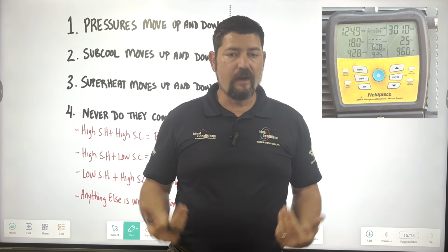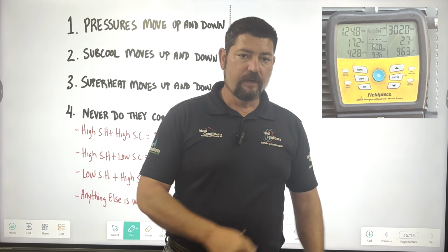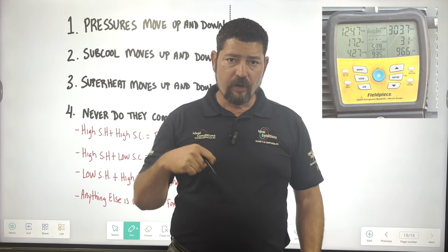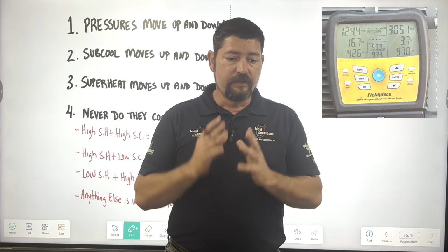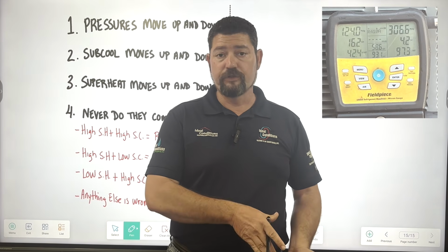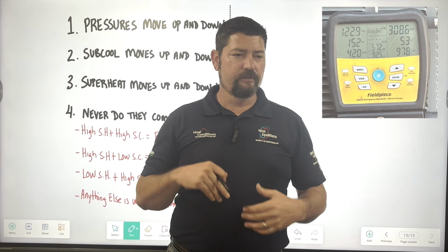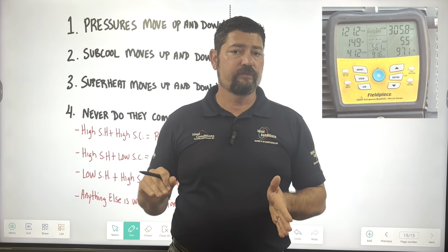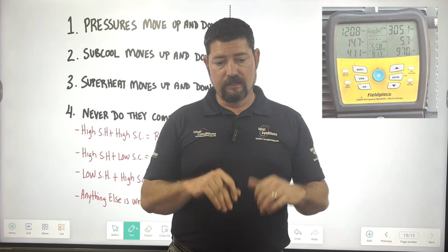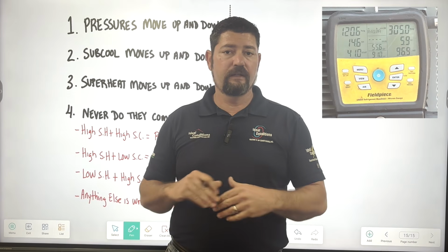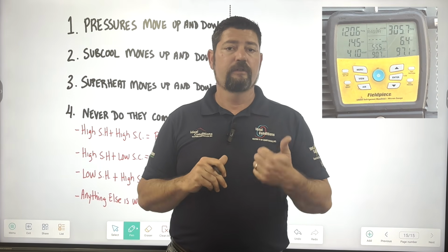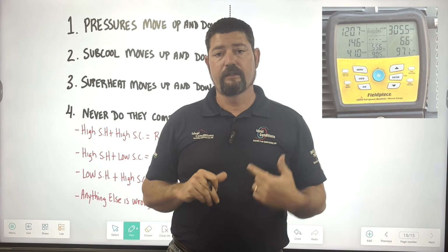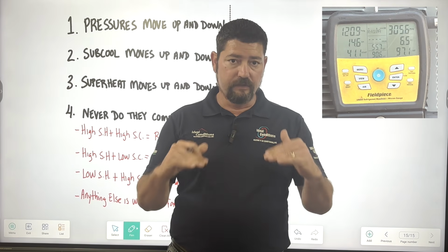Also, there can just be air in your lines when you're hooking these hoses up, and if you're not purging them properly with the refrigerant in the system, you could be introducing that air and moisture. Also, if you pull vacuums too fast, that moisture will freeze. You're not allowing enough time to pull a vacuum down to the proper microns. Even if it shows you the proper microns and it's frozen, that's a lie. You need to let some pressure back in there, thaw it out, and then do what they call a double or triple vac, which is just repeating that same process until you continuously get back to 500 microns.